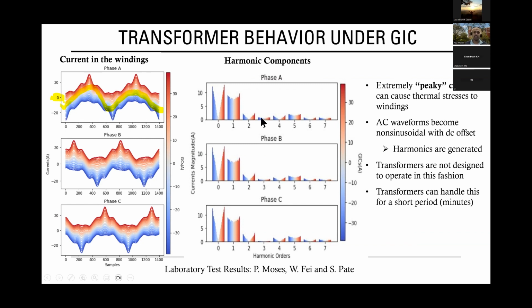And this causes harmonics. This is a harmonic spectrum of these currents. Normally you're supposed to have only this component, 60 hertz. The power system operates on a 60 hertz frequency. The alternating current has a repeating waveform at 60 cycles per second. But when you have harmonics, you have these other frequencies, like musical tones, if you like, that appear as distortions in the waveform. They cause overheating, and the transformer and the power system were not designed for this.